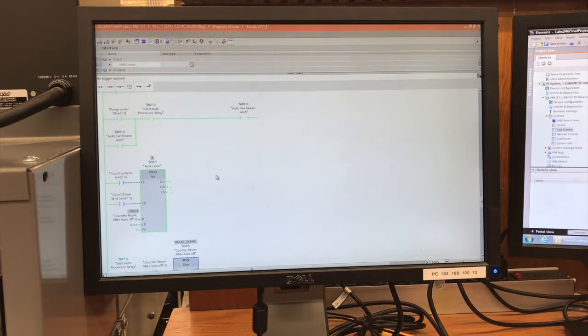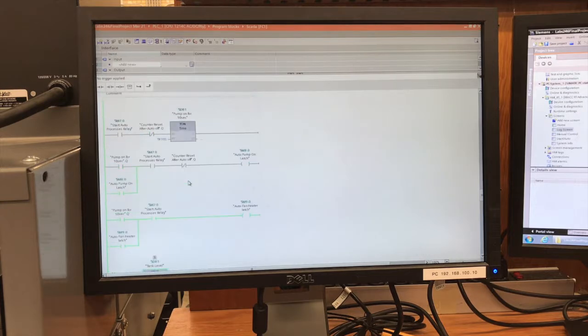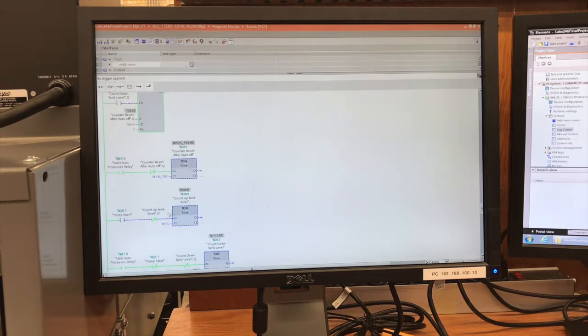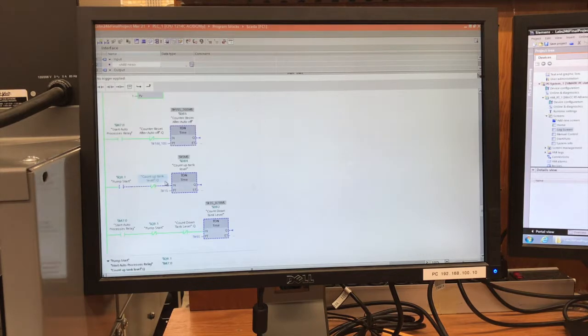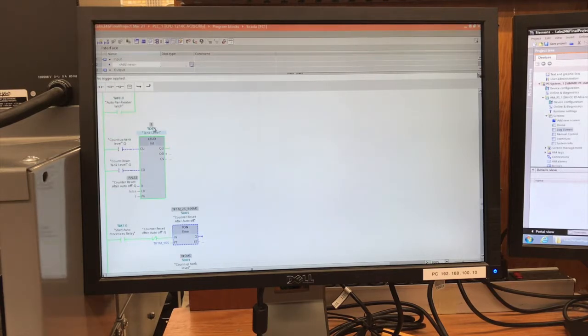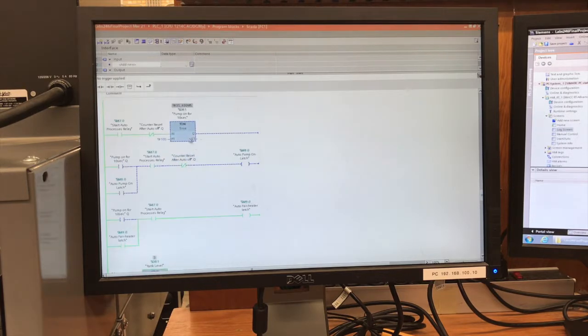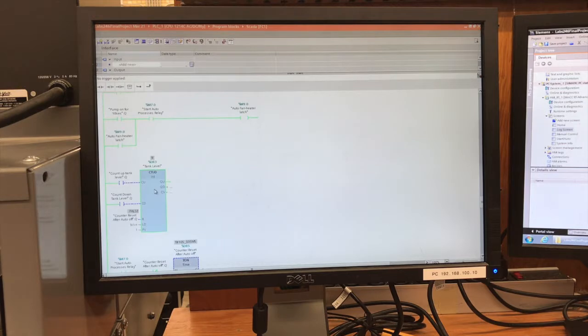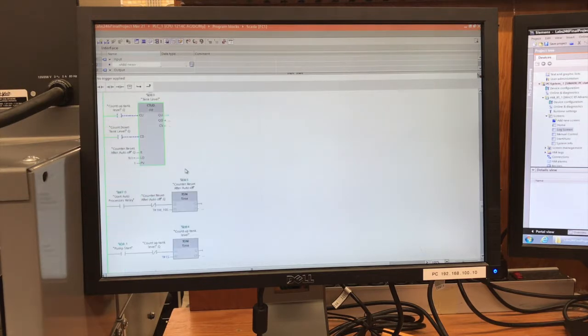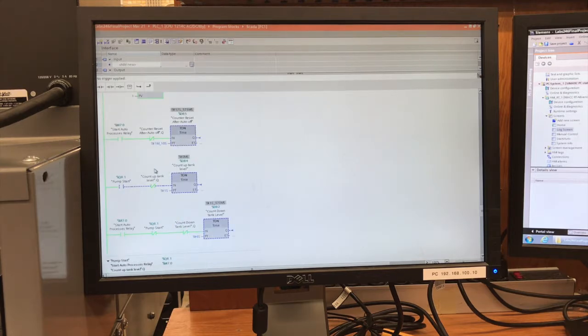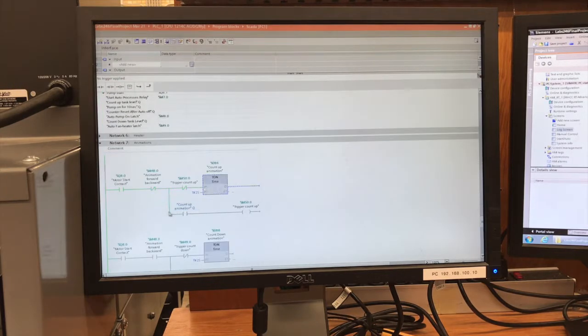Now that we scroll down, we can see the tank level, count up, count down. That's controlled by these timers down here, and accordingly, when the pump is running, it will charge up to its maximum value, and as the 60-second interval elapses, it will decrease back down to its minimum value. This cycle goes on: the pump will start up for 10 seconds. As you can see, it just went up to close to 10, and then every 6 seconds it'll go down 1. So over the process of 60 seconds, which is the countdown tank level timer, it will decrease.